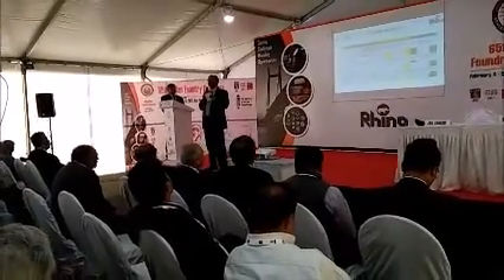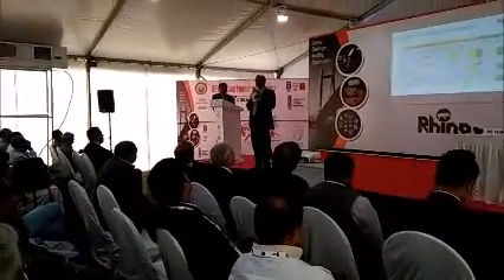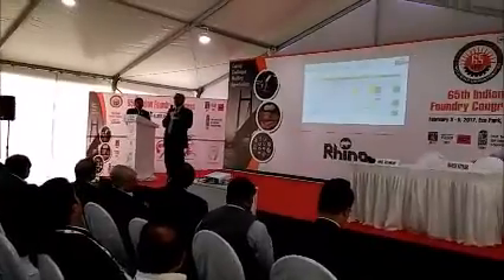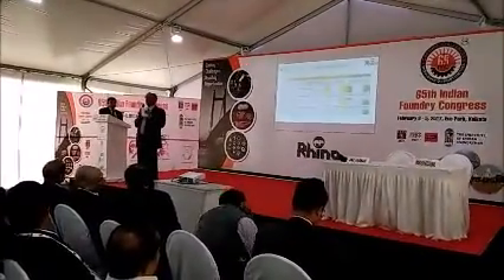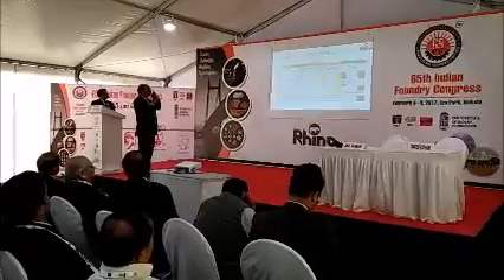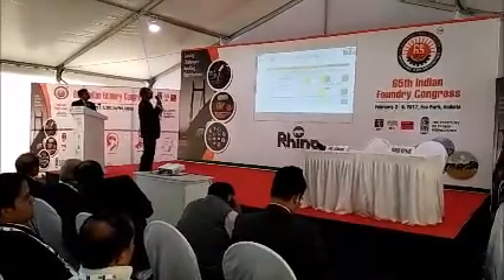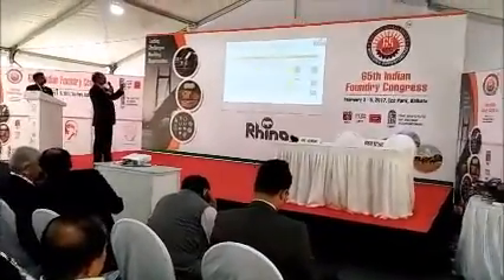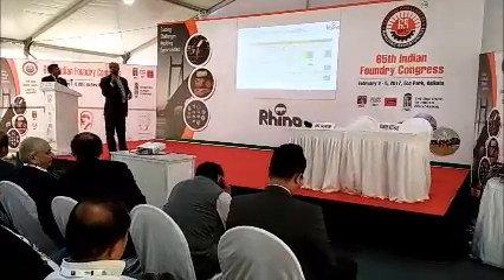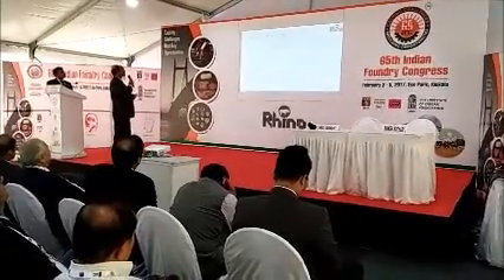you will get an SMS. Automatically, 4 people will get an SMS, and they can reduce the power on any equipment, or the furnace power can be reduced. So you don't overshoot your maximum demand also. By improving the power factor from 85 to 95, you can save almost 200 kVA in your billing.